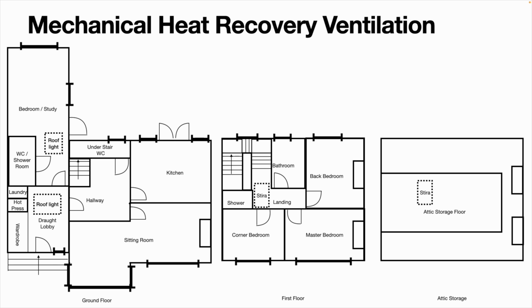In the first instance, you want to figure out where your air is going in and where it's going out. Plus indicates positive pressure, the heat recovery ventilation coming in, and negative indicates negative pressure, where it's getting sucked out. So you want to put your negative ventilation in the WC, shower room, understairs WC, the kitchen space, the bathroom - anywhere there's odor or steam generated. You want to suck that away, you don't want it seeping around the rest of the house.